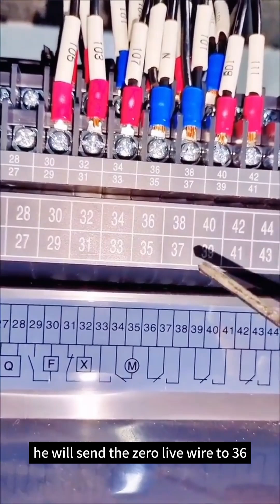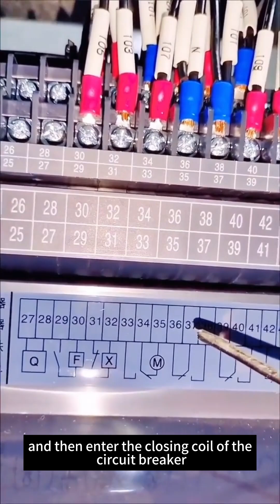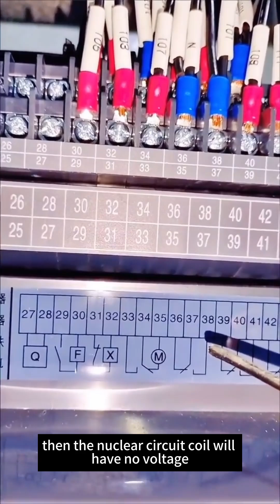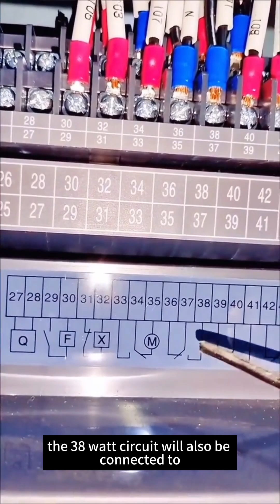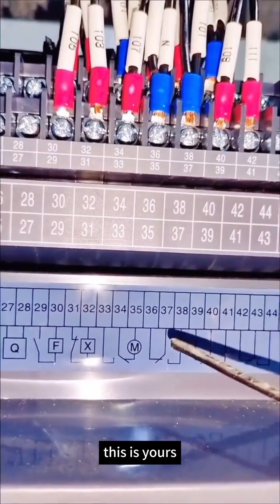That is, when the three phases mix, it sends the live wire to 36, which enters the closing coil of the circuit breaker. Its purpose is to protect the closing coil. When the circuit breaker closes, the 36 circuit will be disconnected, so the closing coil has no voltage. Then after the breaker trips, the 38 circuit will connect to execute the opening coil. That's how it's used.